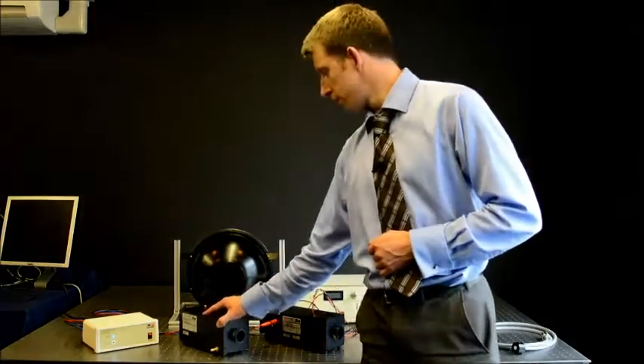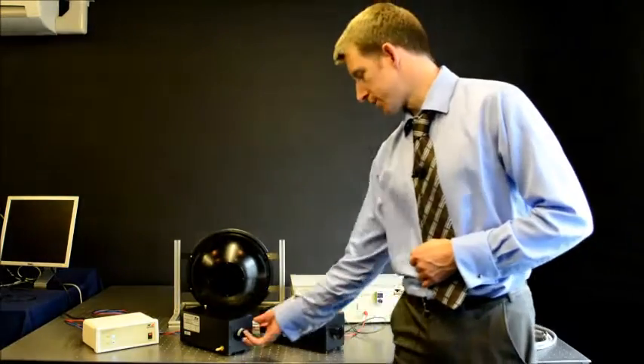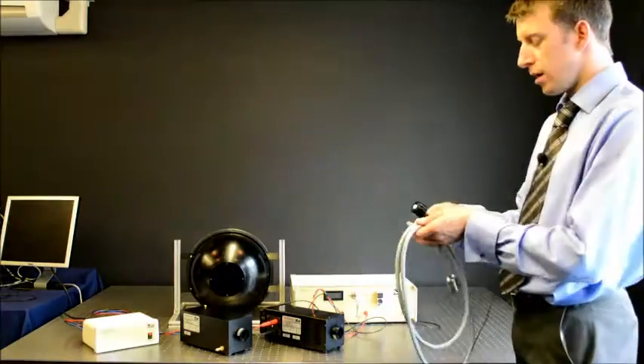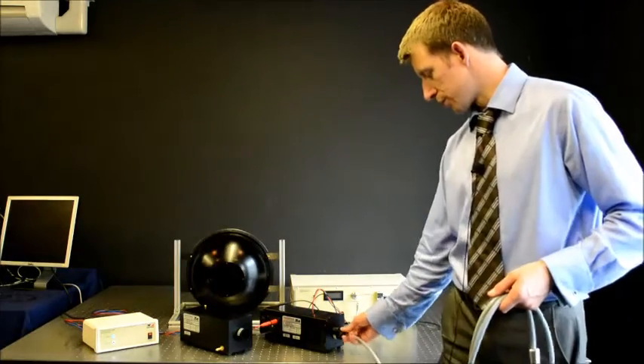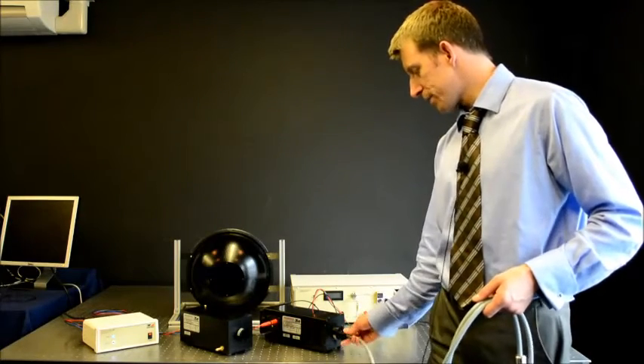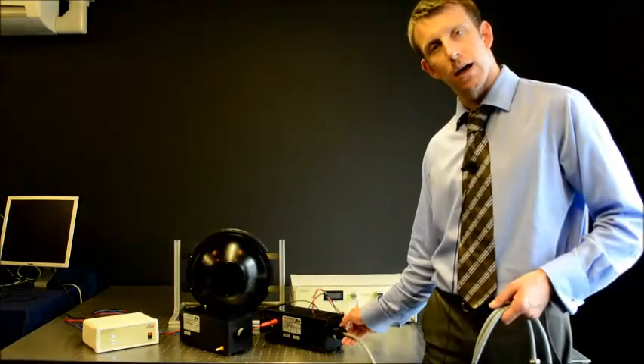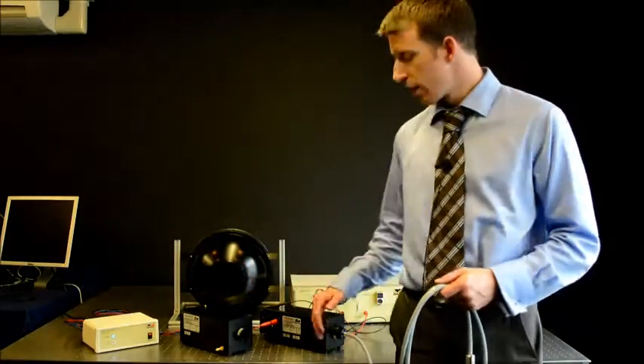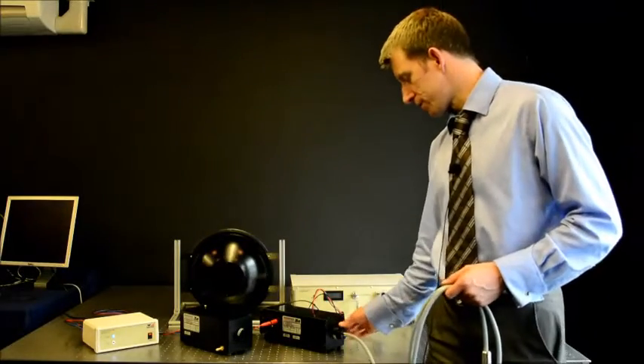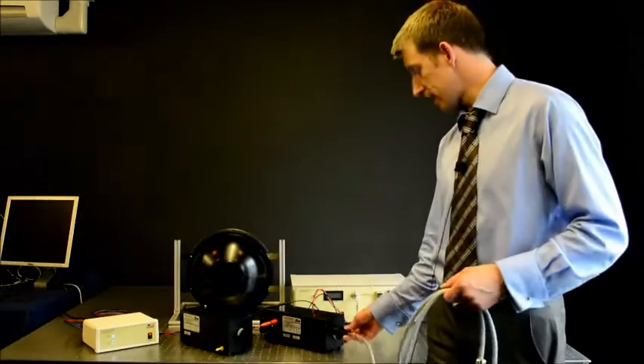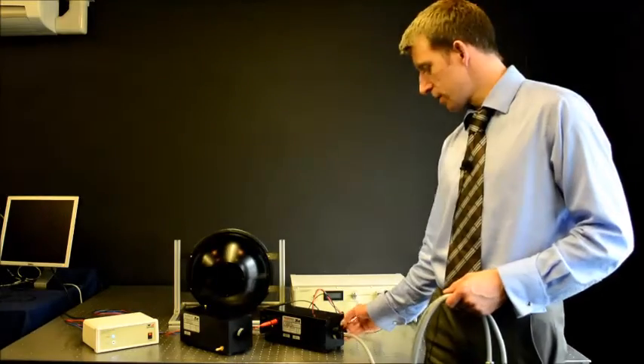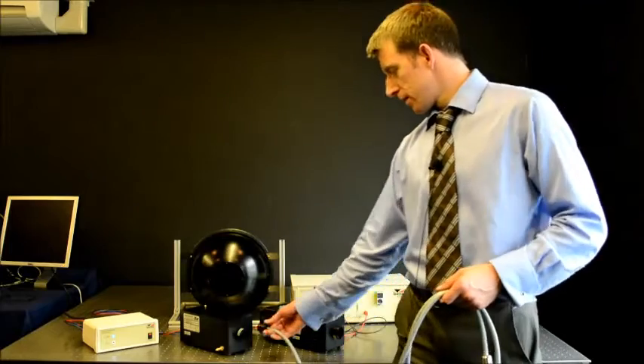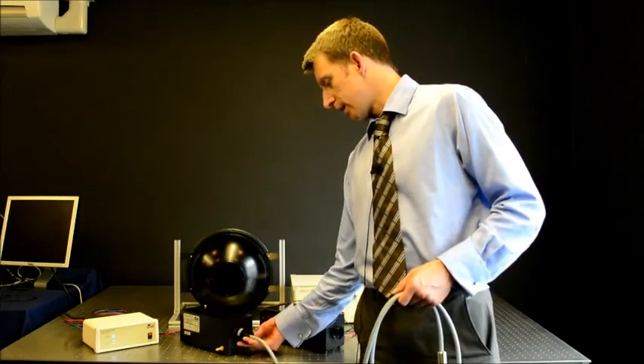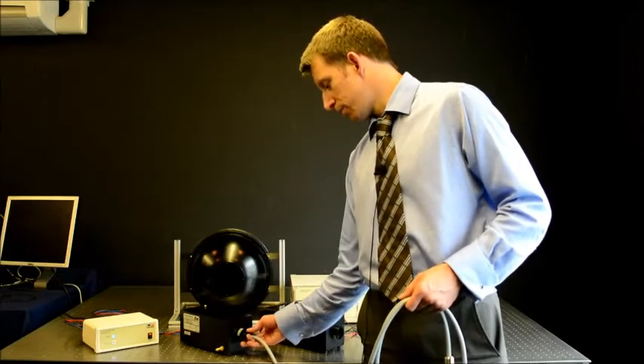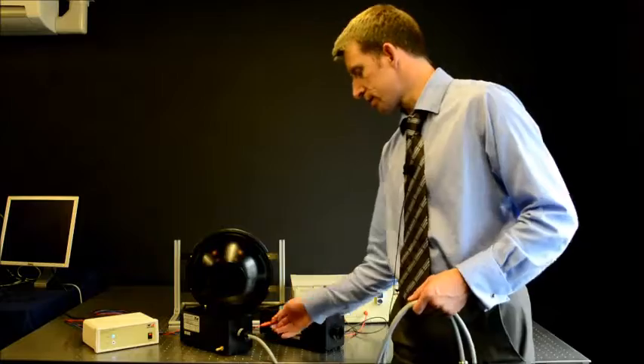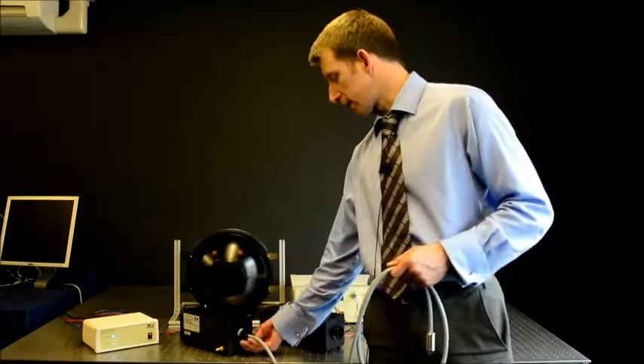In the case of both irradiance standards, a diffuser adapter ring is provided to adapt the D7 diffuser to the source. These sources have been calibrated in spectral irradiance at a well-known distance, 5.5 millimeters from the front face of the source. This is the 5.5 millimeters that the front face of the diffuser is set with respect to the front face of the source when using the DAR. One must make sure that in calibrating that the diffuser is fully pushed in to the DAR and held in place with a thumb screw. And in this manner, a correct calibration will be effected.